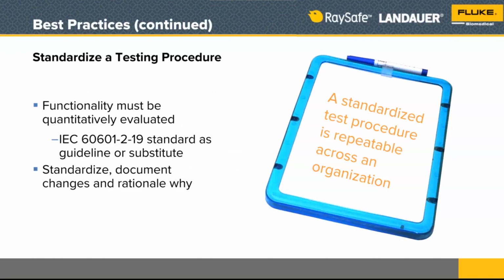We want to standardize our testing procedures. So typically what we would do is we would either follow the international standard or our local national standard, or we would follow the manufacturer's test procedure from the service manual of the infant incubator. So those are the places that we're going to find a test procedure that we can use and standardize on. So that's really important, no matter whether you're documenting your testing with pen and paper and putting it in a file cabinet, oh my God, or whether you're collecting that data more electronically so you can get back to it and easily evaluate failure rates of the different parts of your incubator. Because at the end of the day, it's all about keeping the cost of care down.